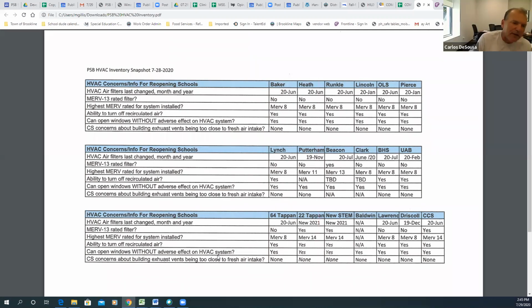So Charlie, if I can add just a couple of things. One is, this is at the equipment level. One thing that we need to do, especially at places such as the Ridley School, where we have demand controlled ventilation, even in classrooms, so we actually have VAV boxes that will close based upon the amount of CO2 in the space, is that those functions should really be disabled so that we have the maximum ventilation that the system can produce. That can all be easily done through the building management system. So that really should be done.